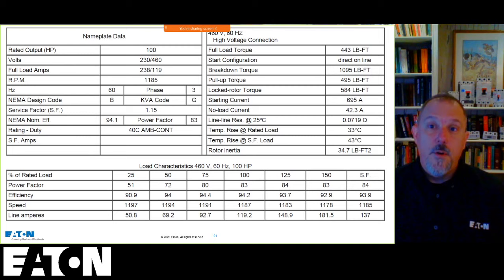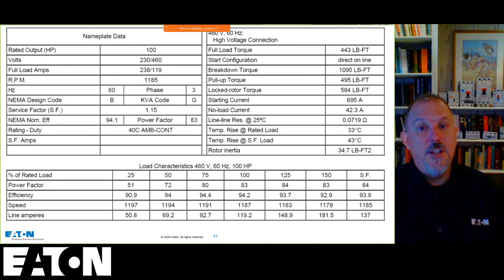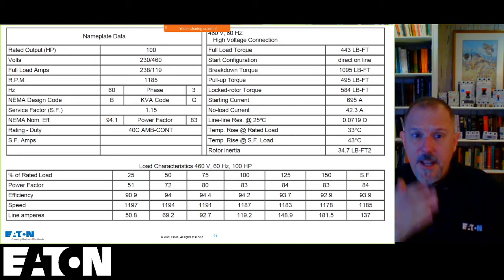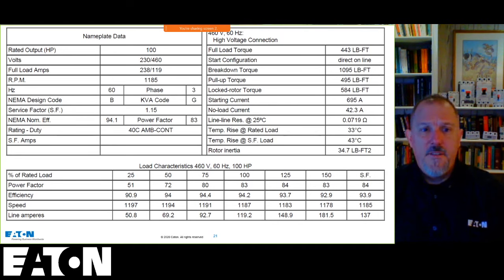One of our discussion points in this session, which I've only got 2 hours, so I can't really get into a lot of detail on everything, but motors are complicated devices, and sizing the motor to the loads to understand the load torque that's needed, the torque that's needed to start a load and keep that load running, and comparing that to the torque capabilities of each of these motors as you get to the different types of applications. So it shows you that if I'm only running that at 50% of rated load, I have a worse power factor than if I run that at 100%.